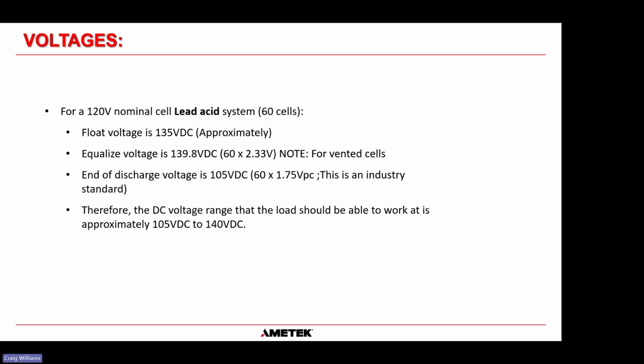So for a 120 volt nominal lead acid system, sticking with voltages, which is 60 cells, the float voltage, which we mentioned at the start of the presentation, should be about 135 volts DC, but you do need to check the battery data sheet to make sure what that should be. The equalized voltage will be about 139.8 volts, which is 60 times 2.33 volts. And remember, that's for vented cells. Most valve regulated lead acid battery manufacturers recommend that you don't equalize those batteries if at all possible, and it will tell you in the data sheet for that battery.